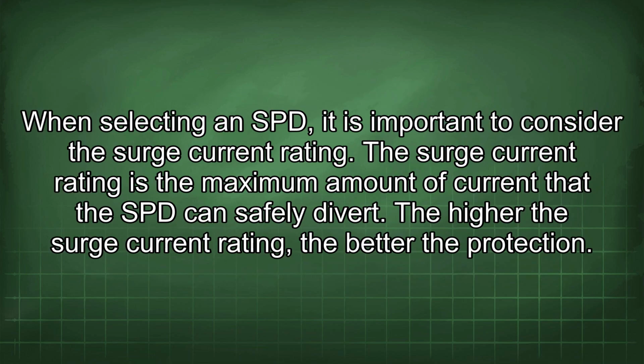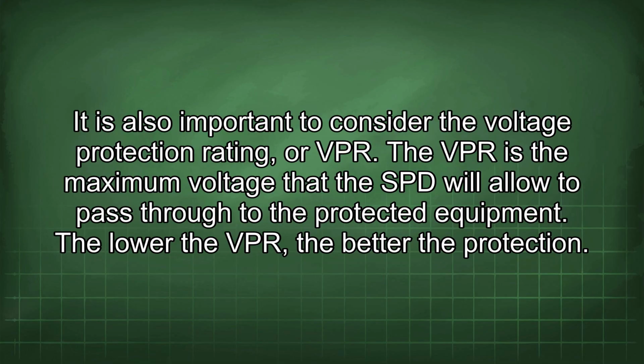When selecting an SPD, it is important to consider the surge current rating. The surge current rating is the maximum amount of current that the SPD can safely divert. The higher the surge current rating, the better the protection. It is also important to consider the voltage protection rating, or VPR. The VPR is the maximum voltage that the SPD will allow to pass through to the protected equipment.